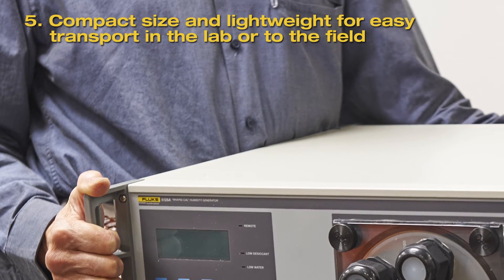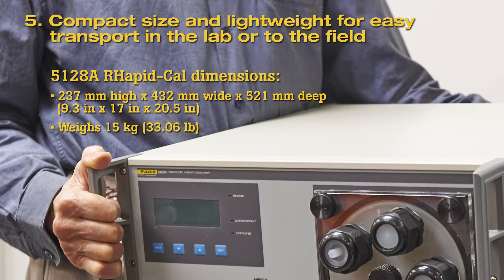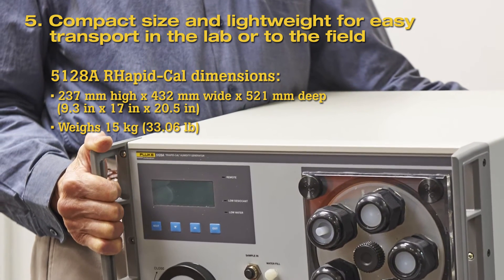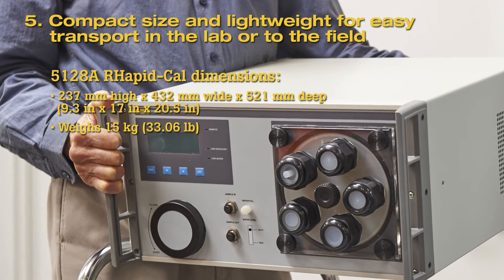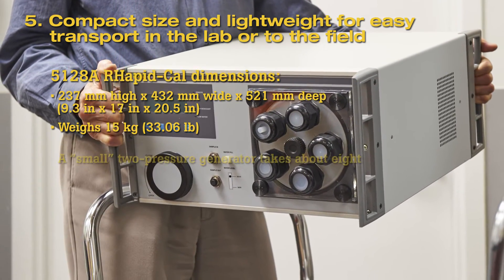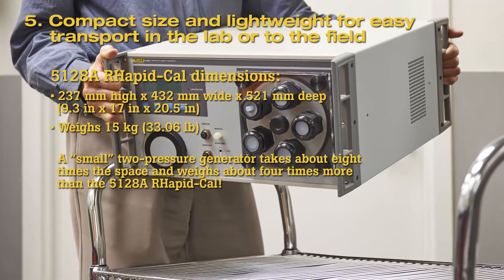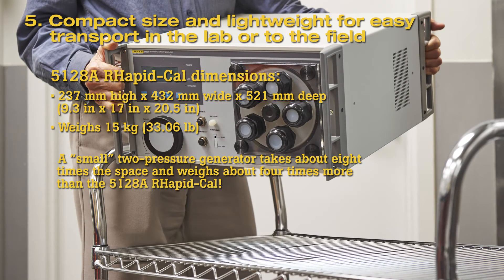Fifth, compact size and lightweight for easy transport. It can be easily carried to any desired bench space in the lab or transported on-site to a field work location. In comparison, a two-pressure humidity generator is practically limited to laboratory use because of its large size — it includes a generator, compressor, and supporting equipment. A small two-pressure generator requires about eight times the space that the 5128A RHapid-Cal does and weighs about four times as much. The 5128A is lighter than most transportable humidity generators in its class, easily placed on a small cart for plant-wide transport, and a convenient wheeled transport case is offered for shipment or transport to on-site calibrations.